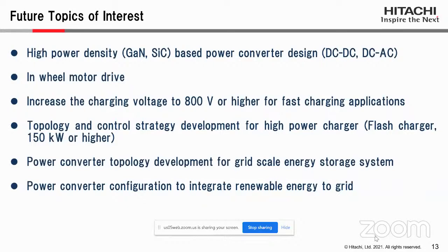That is another key area of research. Another fast charging application is for buses, because for highway or local intercity buses, we need to charge at a very short time. There are two cases for bus application: when they reach a terminal, they have a longer time to charge, but for intermittent charging at a public stop, they need to charge at a very fast pace, about 10 to 15 seconds. For this application, ABB has already developed a 600 kilowatt flash charger, charging at 600 kilowatt for 10 to 15 seconds. For such applications we need a lot of power in a very short time, so we need to develop our technologies accordingly so it doesn't affect the power system, because taking a lot of power in a short time may affect the power distribution.